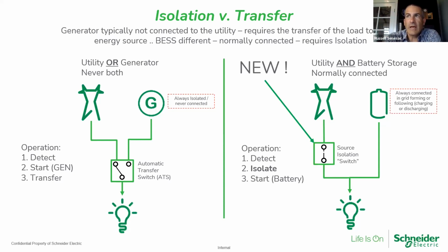When you look at a battery as being normally connected, when the utility fails, that battery has to have a way of disconnecting from the grid to create energy the building can use. Because if you can't isolate or disconnect from what you're connected to, you're trying to start everything instead of just the building. You don't have enough power to start the grid. You can't start your house and your neighborhood block all at the same time. You have to isolate from the block, get it to just your building, and then you can create energy to power the load.